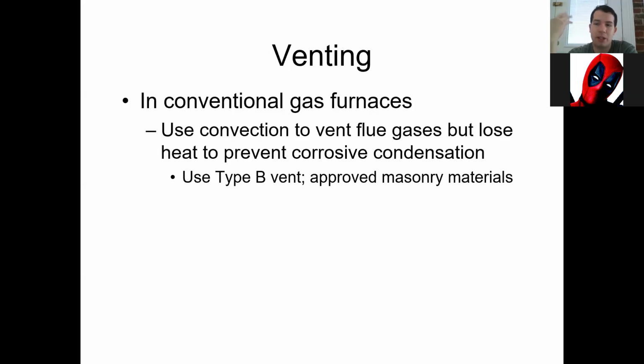Those could be in the crawl space or the attic, where we don't want those kinds of things escaping, because not only are they toxic, but they're high temperature. And with a high temperature, if you've got it where it starts drying out a section of wood, or it starts eating up some mortar or something like that in a chimney, it can just be really catastrophic as far as the amount of damage it can cause, just because someone wanted to put 2 screws in instead of 3. They didn't want to secure it all the way down.